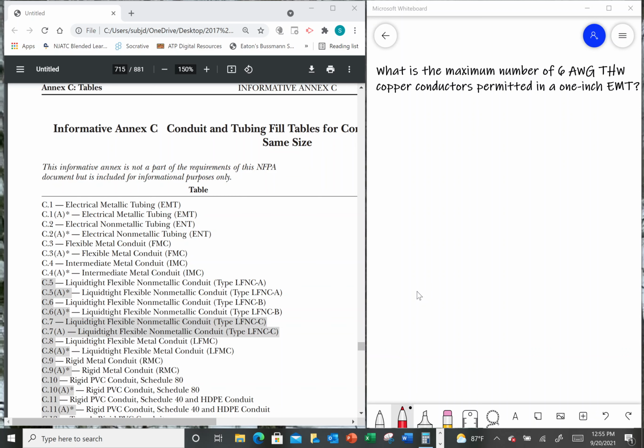Alright, in this video we are going to address pipe fill or conduit fill. Just like before, if you watched my video on box fill, we talked about Table 314.16(A) and 314.16(B), where 314.16(A) was if all of my wires were the same size, I could just go to 314.16(A) and figure out what size box I needed. Well, there's a similar situation when it comes to pipe fill. In conduit fill, my insulation type is important, because the insulations are different thicknesses and take up more room in the conduit.